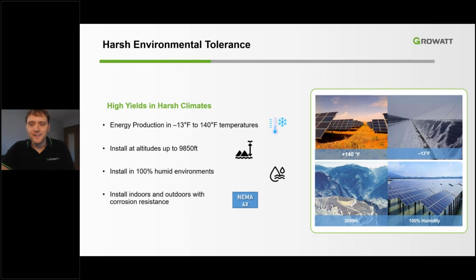The MIN inverter can be installed in harsh environments and operate in temperatures from -13 degrees Fahrenheit to 140 degrees Fahrenheit. It can be installed at altitudes up to 9,850 feet, in 100% humid environments, and indoors or outdoors with corrosion resistance thanks to the NEMA 4X rating. The research and development team really understood the needs of the North American market and tailored this inverter to meet those needs.